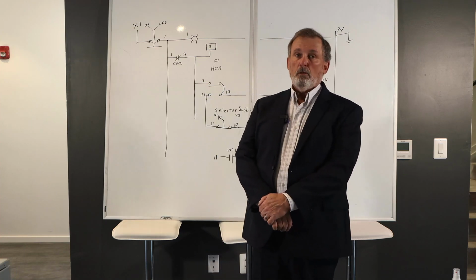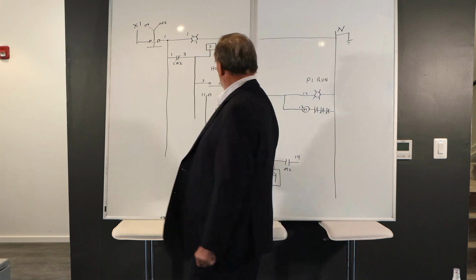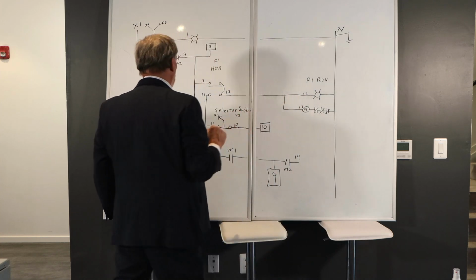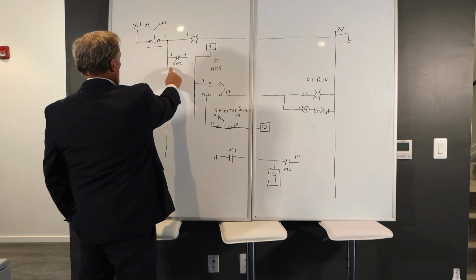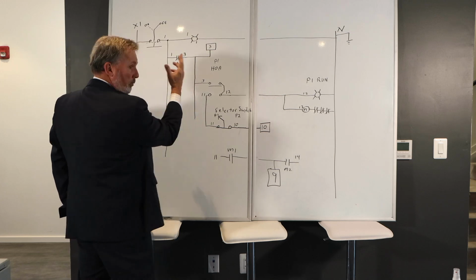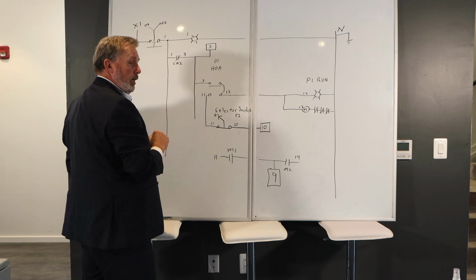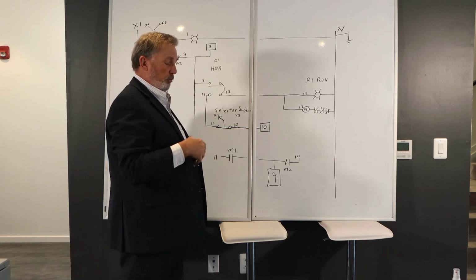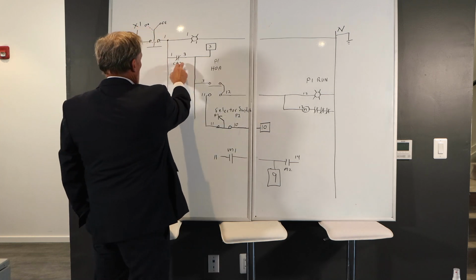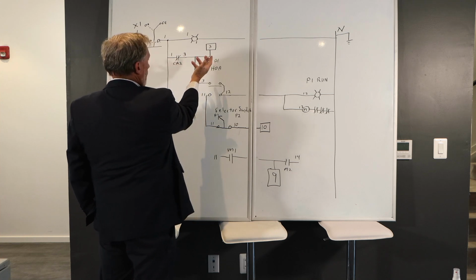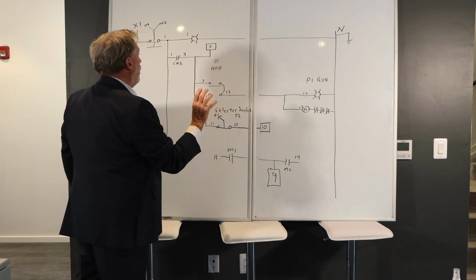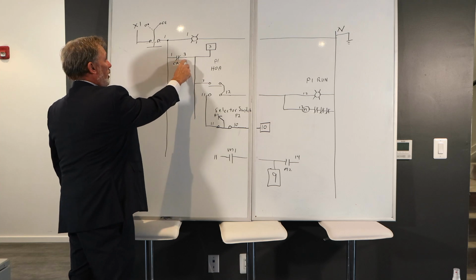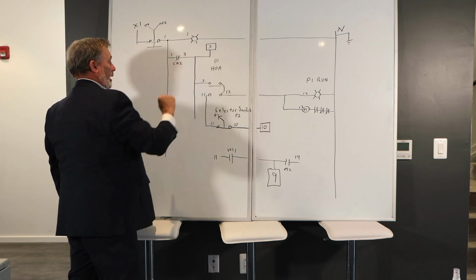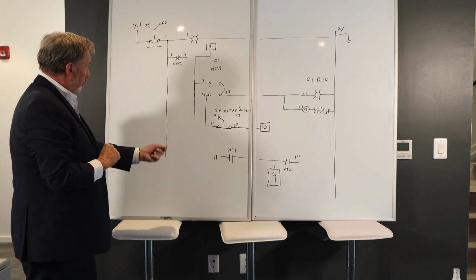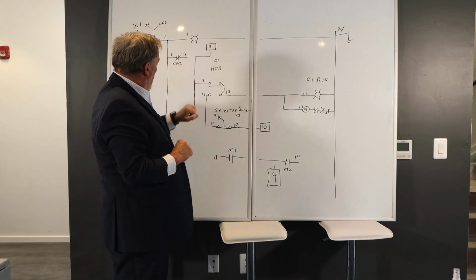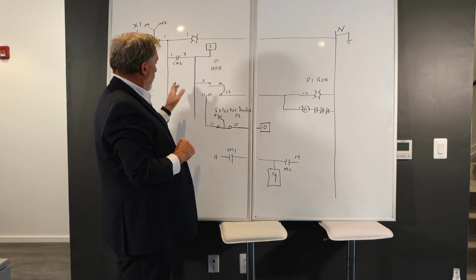Now, next thing we want to take a look at on the ladder diagram is how we're actually getting power to the pump run point. I've got a control relay here that's going to come up later, normally closed contacts. Now, these contacts are going to open up if we have an alarm. From there, I'm picking up a constant hot. As long as I have no alarm situation, I have a constant hot on wire number 3, which has an external terminal. Okay? From there, I go to an HOA switch, hand-off-auto.